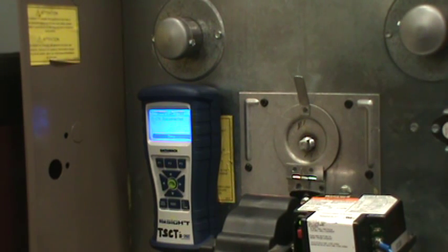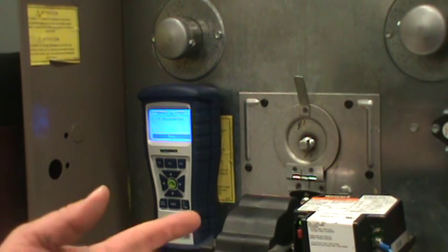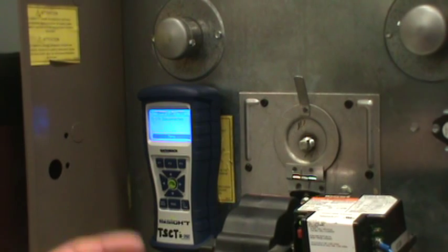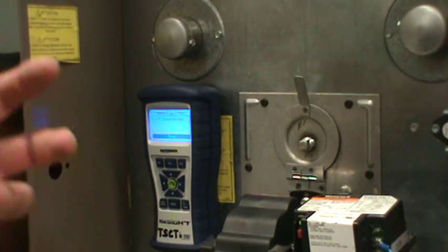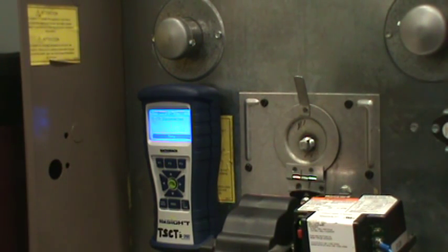So what we're going to do is get the overfire draft. We have to make sure our overfire draft is around negative 0.02. That'll be right on. An overfire draft should be measured in the beginning when you fire the unit up. You want to have a negative environment at fire. If it's not negative over fire, you're going to have a pulsating, rumbling, soot. It can really rumble, make a lot of noise, and you'll end up with soot coming out and getting into your airstream.